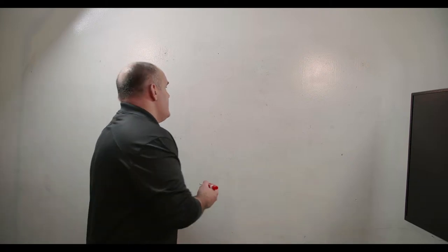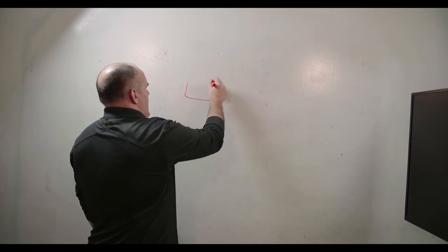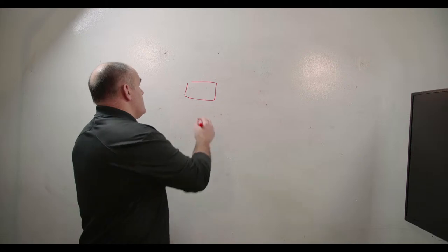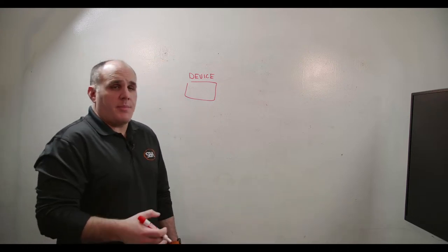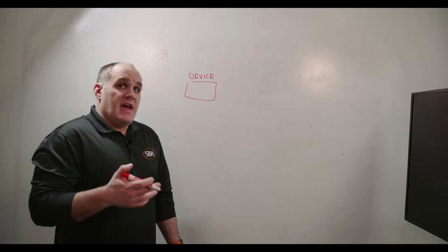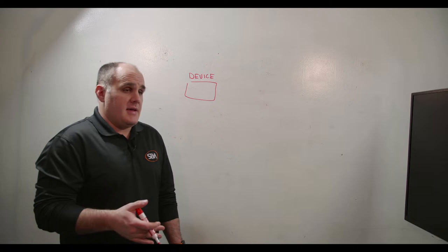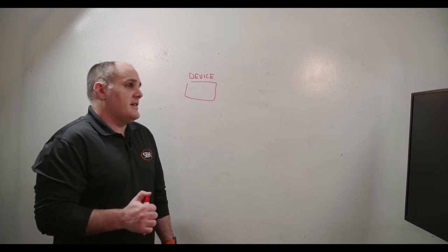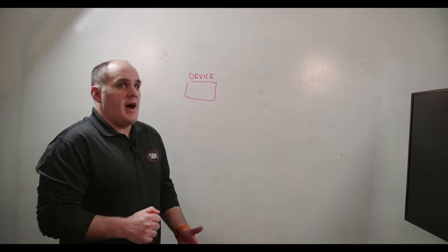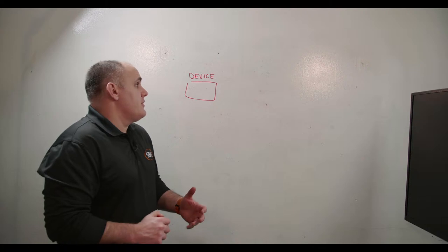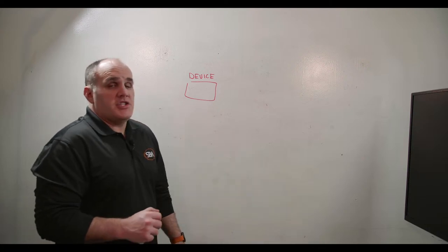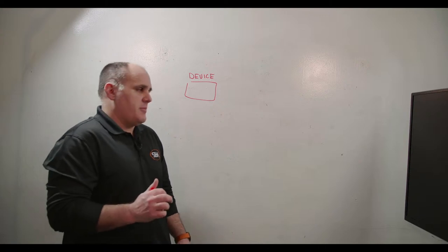BACnet is an object-oriented model. For those of you who don't understand what an object-oriented model is: we have object types. The primary object type in BACnet that we're mostly concerned with is called the device object. I'm going to be teaching you about object types, properties, and services. I won't be talking about BACnet MS/TP and BACnet IP in this video. A lot of the issues I see — especially in integration — have to do with people not understanding the BACnet object model.